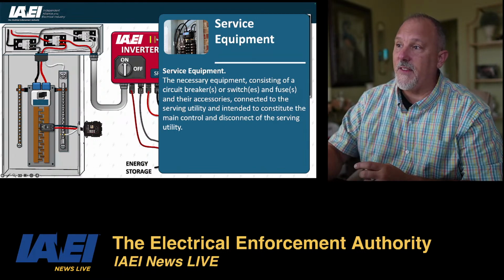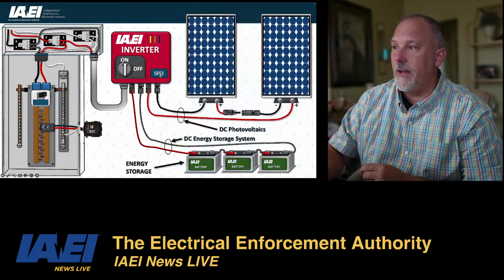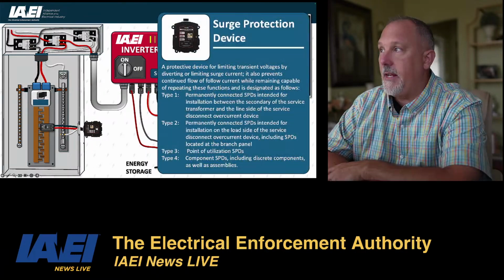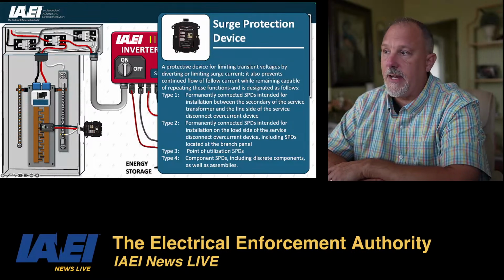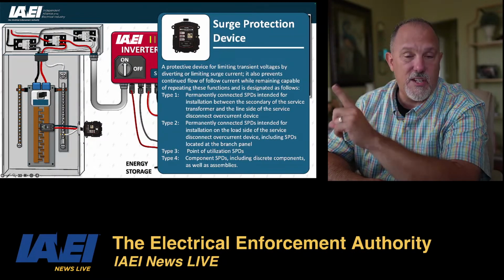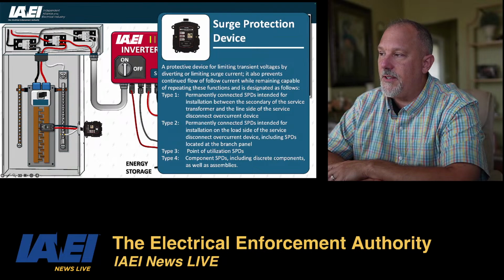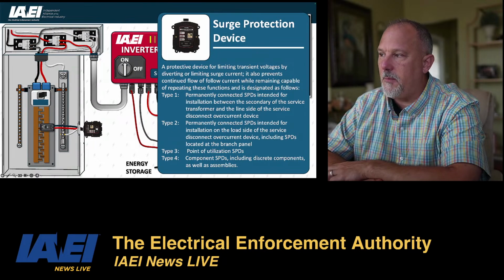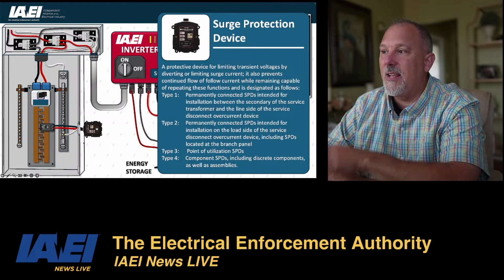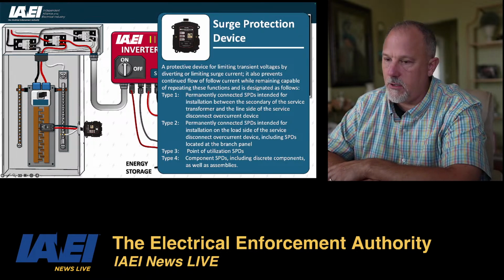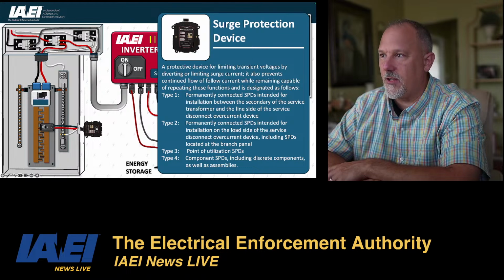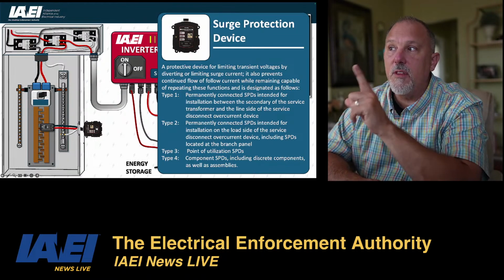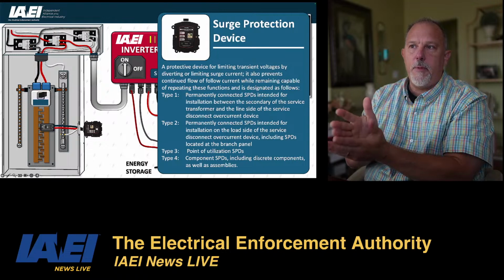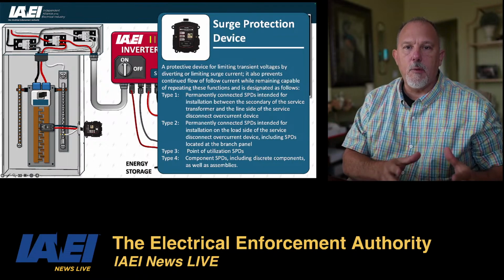You're also going to have surge, right? So an SPD is going to be needed. So you need a surge protective device. This can be a type 1 or a type 2 because a type 1 is permitted to be connected on the load side of the service disconnecting means or on the line side. But typically you'll see a type 2 in this location. So that's required as well. So the important thing is, once you call it service equipment, there are a lot of other requirements you need to follow.